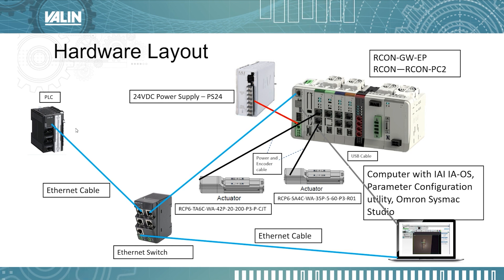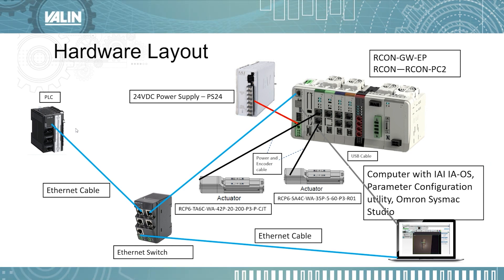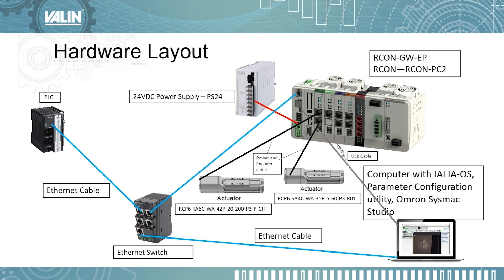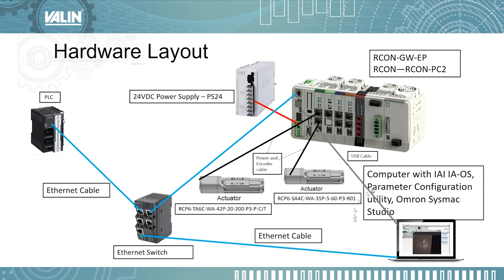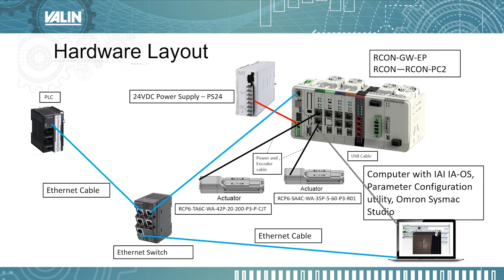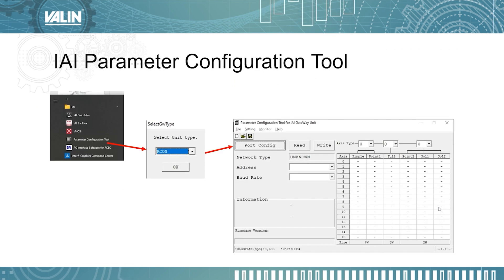This PLC can be any PLC with an Ethernet IP scanner — it can be Mitsubishi, Siemens, or Allen Bradley; they all will work. I also have my computer connected via USB cable to the RCON gateway, and an Ethernet cable from my computer to the switch. The software I need is IA-OS and the Parameter Configuration Utility, and I'm using Omron Sysmac Studio to manipulate the data and show how it works. First and foremost, you need to launch the Parameter Configuration Tool.